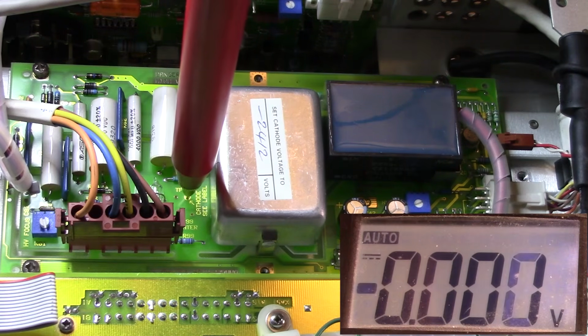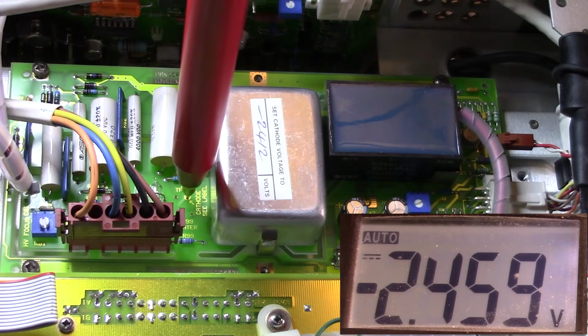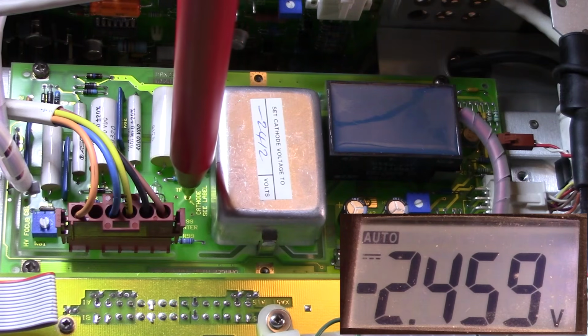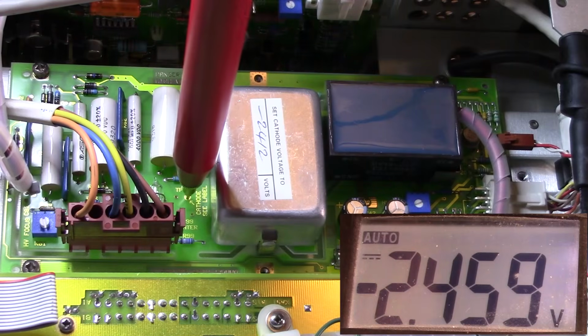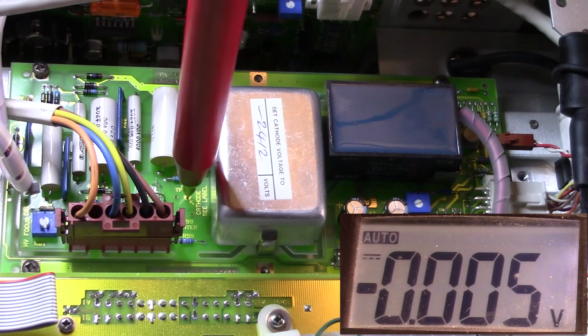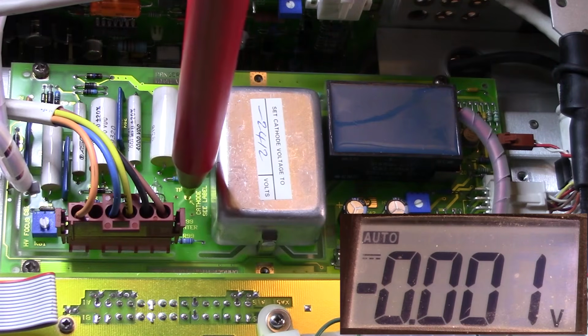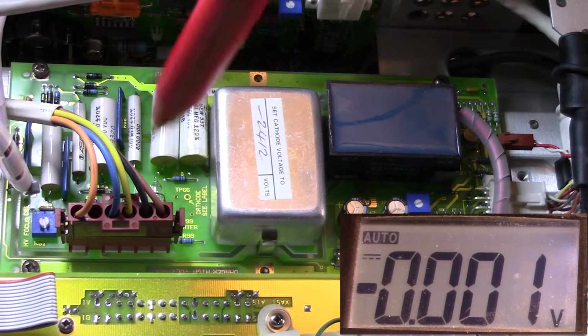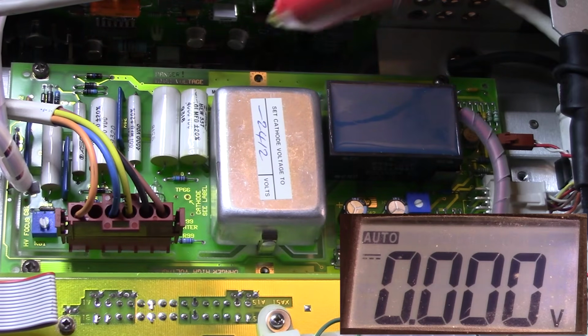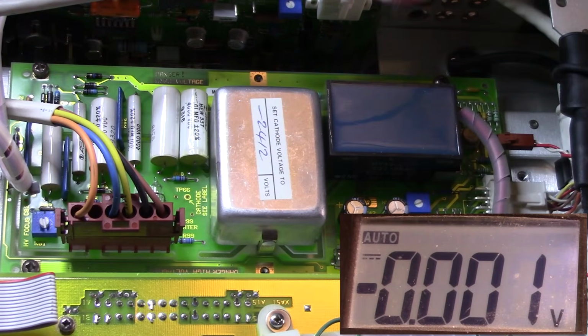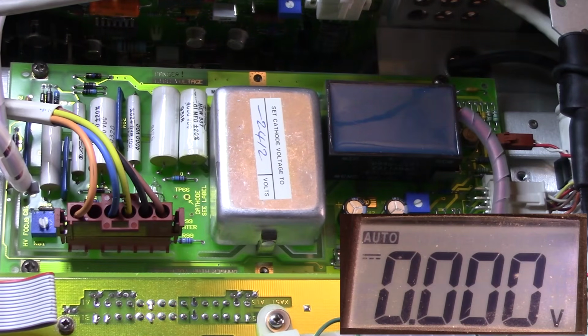But if we turn it on now, all right, we can see minus 2459, which is a little bit more minus than what the tag here is saying. But it is at least showing that we're getting voltage there. So now, if we turn that off, the next test point is test point 99, I think it is, which is the heater. Now, that test point, let me just check the schematic again.